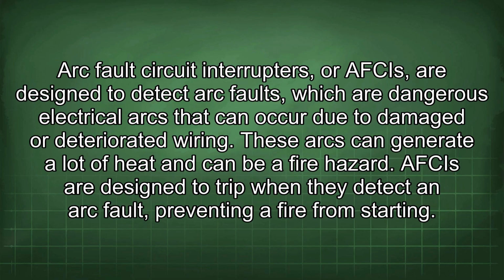Arc fault circuit interrupters, or AFCIs, are designed to detect arc faults, which are dangerous electrical arcs that can occur due to damaged or deteriorated wiring. These arcs can generate a lot of heat and can be a fire hazard. AFCIs are designed to trip when they detect an arc fault, preventing a fire from starting.